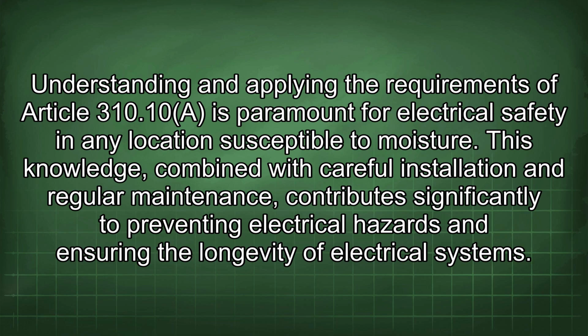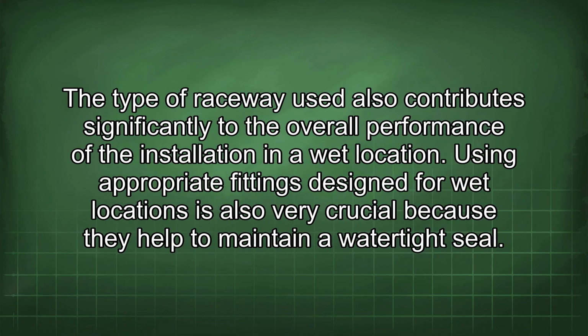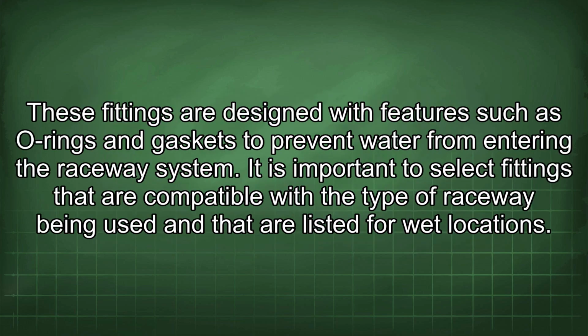Understanding and applying the requirements of Article 310.10 is paramount for electrical safety in any location susceptible to moisture. This knowledge, combined with careful installation and regular maintenance, contributes significantly to preventing electrical hazards and ensuring the longevity of electrical systems. The type of raceway used also contributes significantly to the overall performance of the installation in a wet location. Using appropriate fittings designed for wet locations is also very crucial because they help to maintain a watertight seal. These fittings are designed with features such as O-rings and gaskets to prevent water from entering the raceway system.